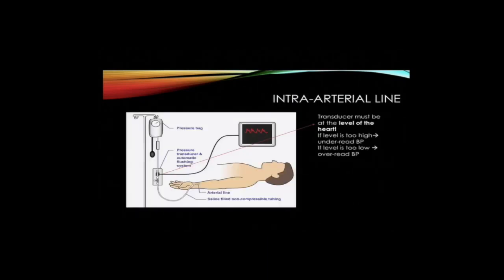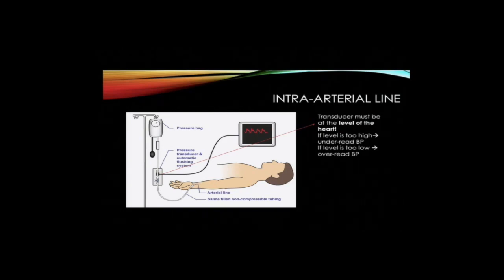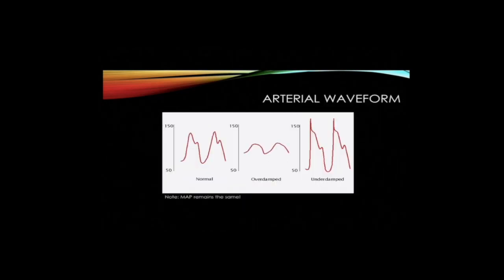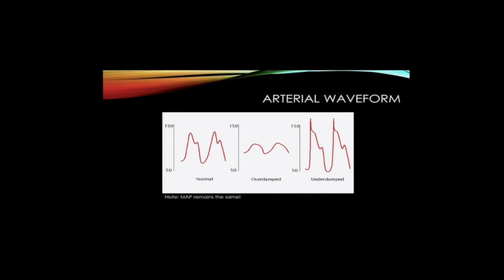The arterial catheter is one of the most common interventions in the ICU and allows invasive blood pressure monitoring. The pressure transducer must be placed at the level of the heart. If the level is placed too high, this will lead to an under-reading of the blood pressure. If the level is too low, this will cause an over-reading. Transducer kits are designed to provide optimal damping of the pressure waveform. An under-damped trace will display an inaccurately high systolic blood pressure and an inaccurately low diastolic blood pressure. The converse is true in an over-damped trace. In both cases, the mean arterial pressure should be accurate.